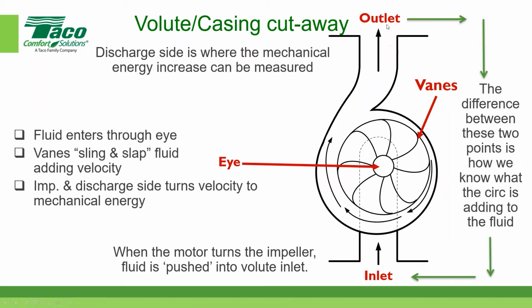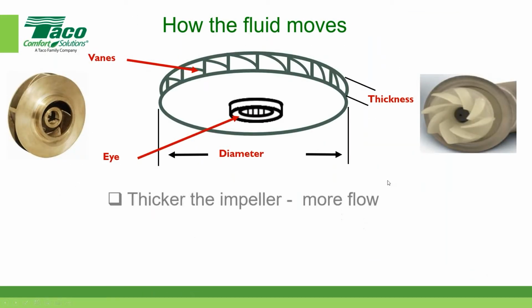And I want to show you here the difference between the outlet and the inlet. When we measure that difference, we can see exactly what the circulator is imparting on the fluid as far as additional pressure. Okay, we witness the mechanical energy by means of pressure gauges. So, not a play on words, but an understanding: we're adding mechanical energy to the fluid by means of the impeller actually spinning, creating centrifugal force. Okay. A couple other things I'll use as reference.